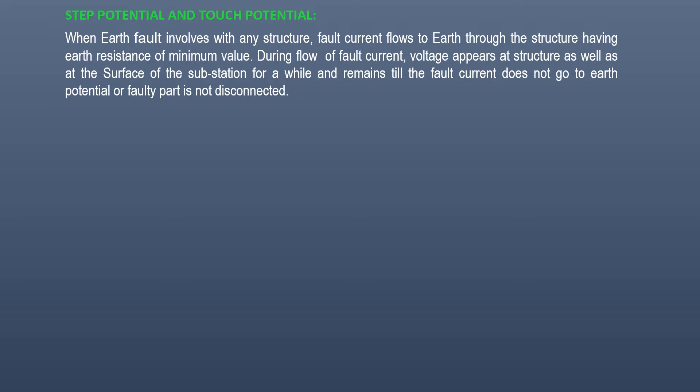When earth fault involves with any structure, fault current flows to earth through the structure having earth resistance of minimum value. During flow of fault current, voltage appears at structure as well as at the surface of the substation for a while and remains till the fault current does not go to earth potential or faulty part is not disconnected.